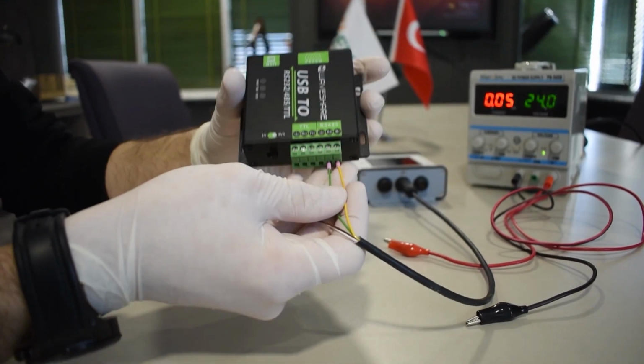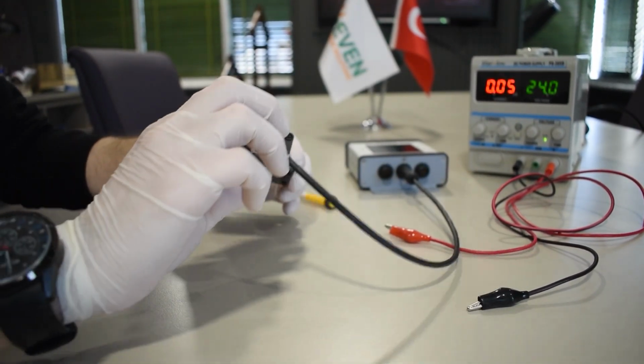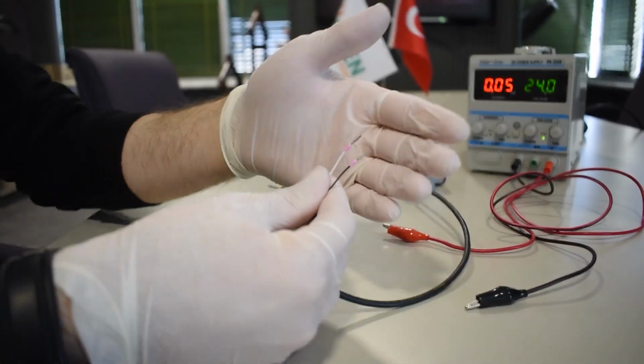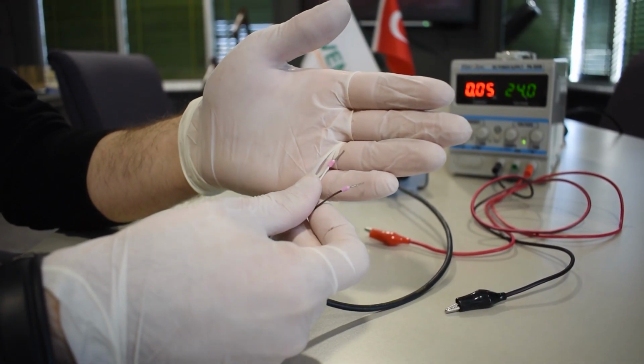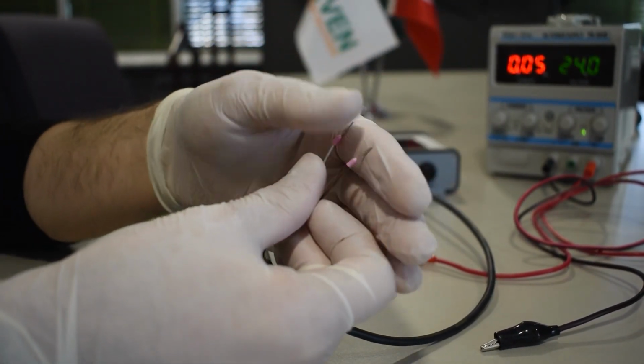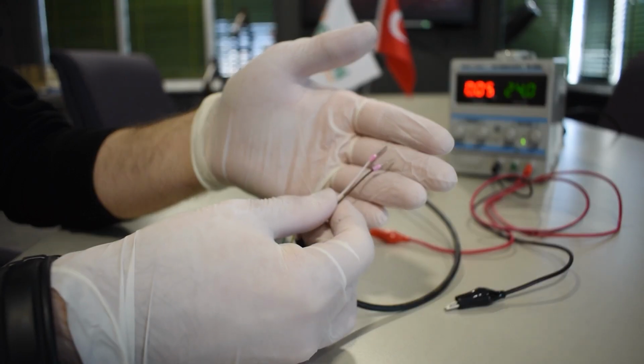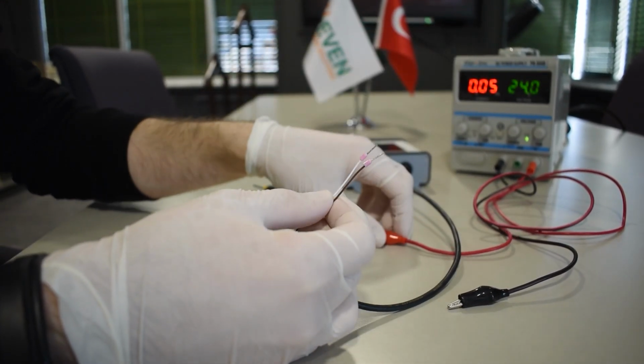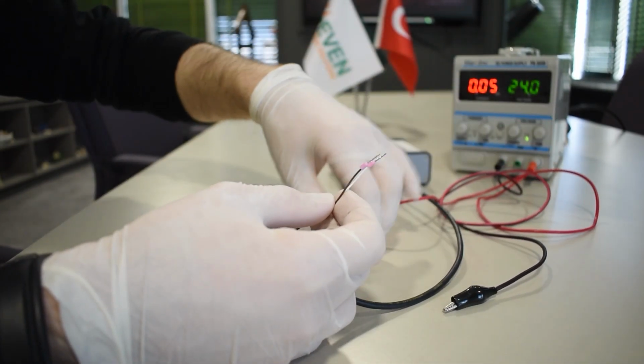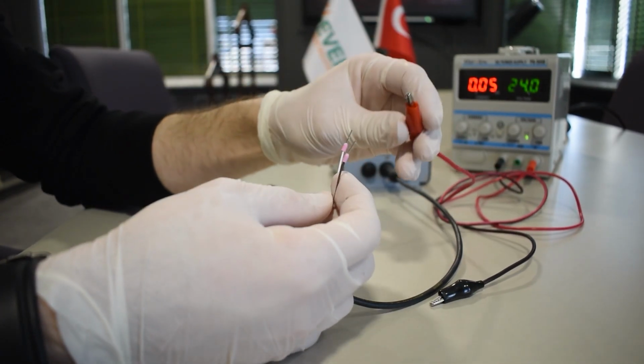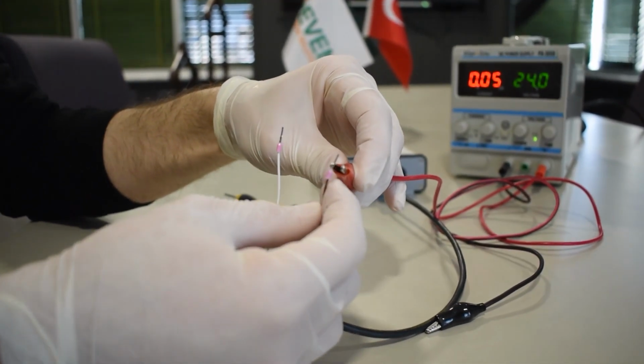The brown wire of the output cable of the sensor box is the power plus wire, and the white wire is the power minus wire. Our sensors work with direct current between 12 volt and 30 volt. The recommended voltage is 24 volt.